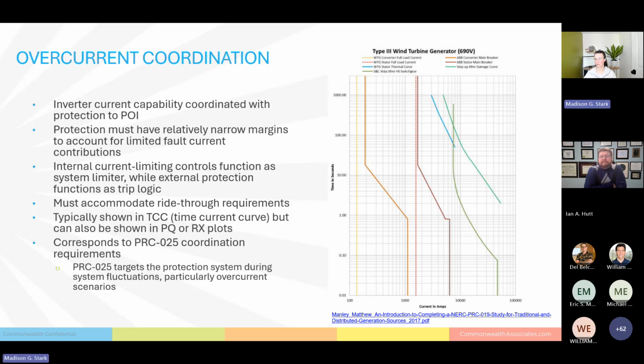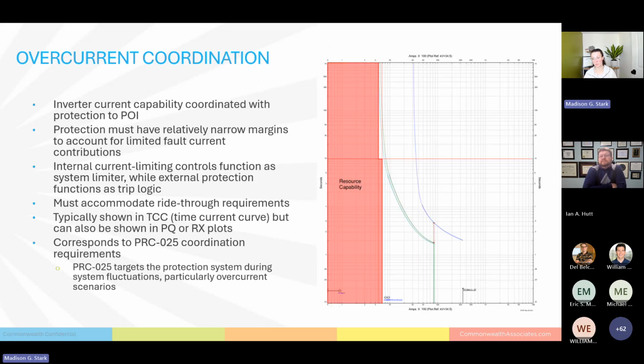Mike had a question in the Q&A portion. As far as adding time between initiation of trip and breaker opening, that margin you're looking for, it's not necessarily specified in PRC 19, but it's an element of all protection and coordination efforts. One of the things you can do, and I took all the identifying details out so it's not specifically labeled here, is calculate what that time looks like between your relay response time, your opening time, the margin of error you include in both of those, and all your other little bits that add up. Then you create basically a project margin for your site. And that time margin is what you determine.